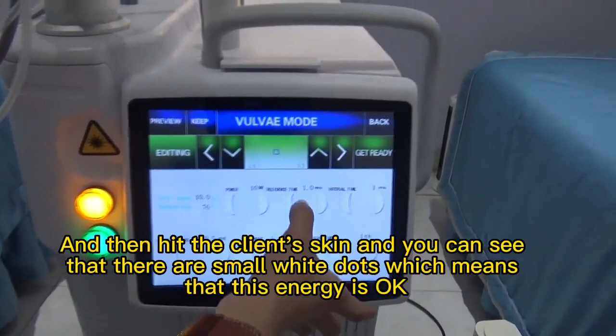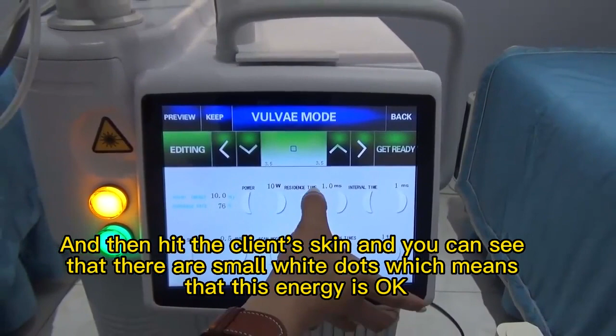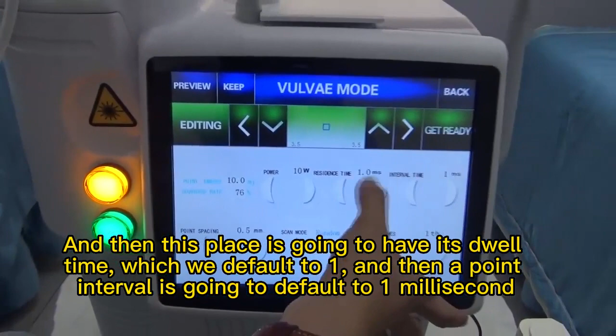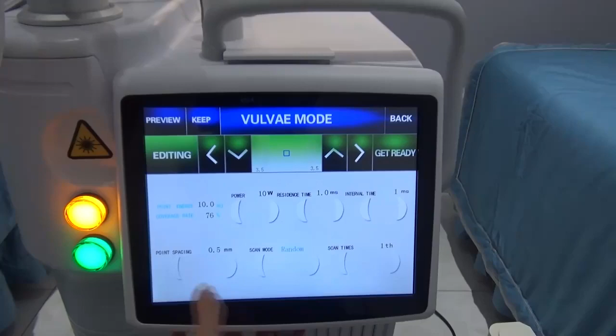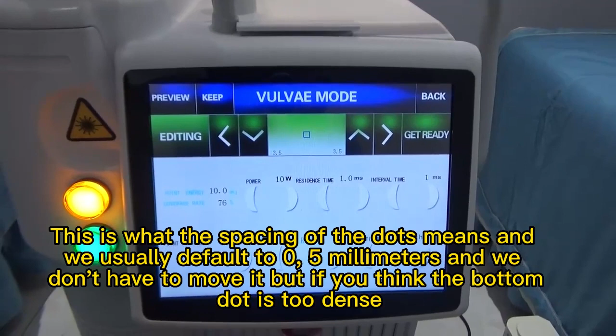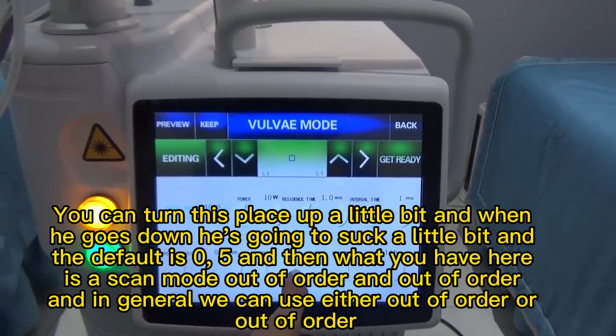This is what the spacing of the dots means, and we usually default to 0.5 millimeters, and we don't have to move it, but if you think the bottom dot is too dense, you can turn this place up a little bit, and when it goes down it's going to suck a little bit, and the default is 0.5. Then here you have a scan mode, ordered or out of order, and in general we can use either one. This place represents the number of scans and the default is 1.